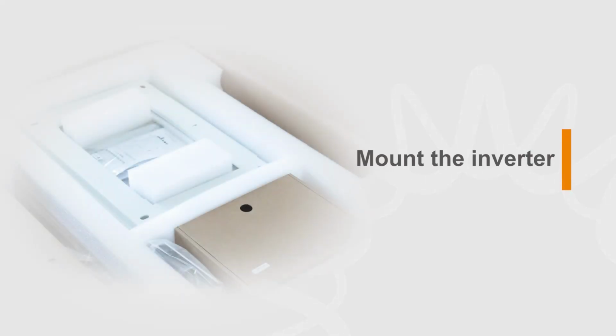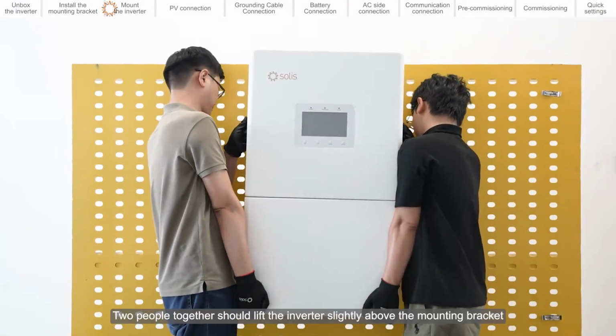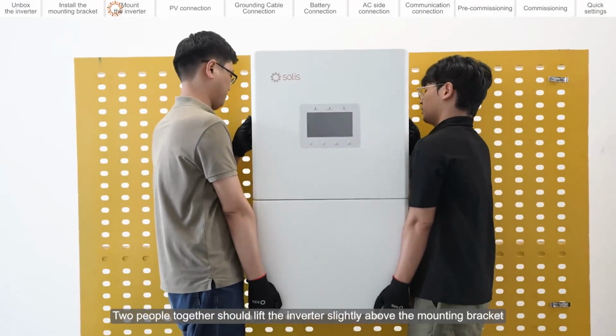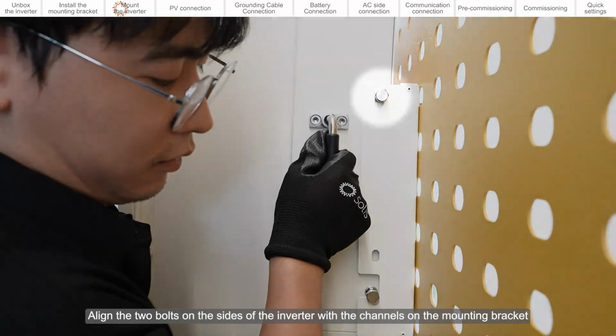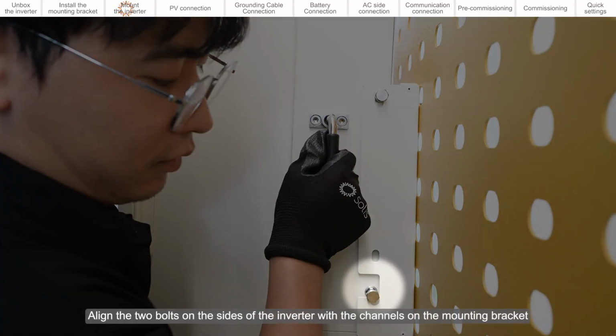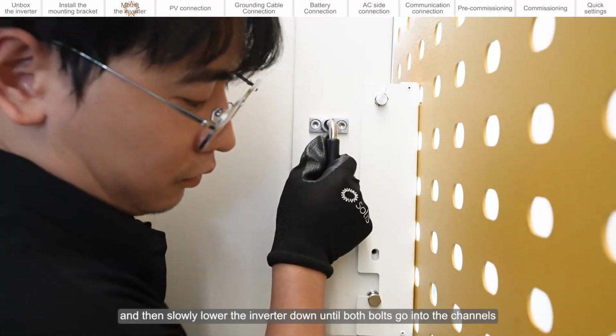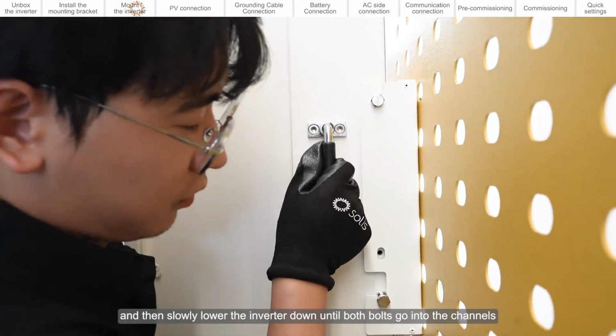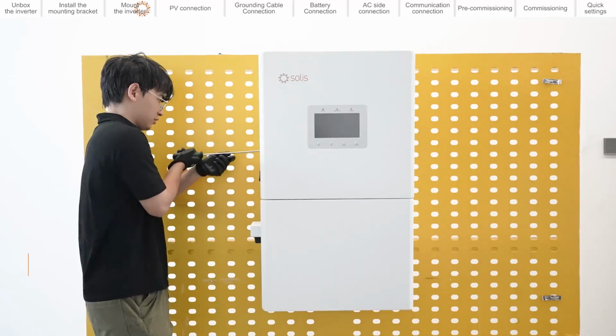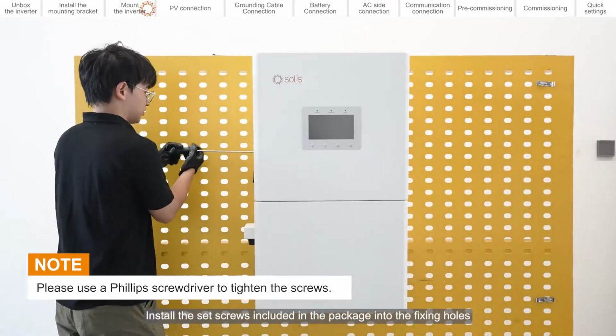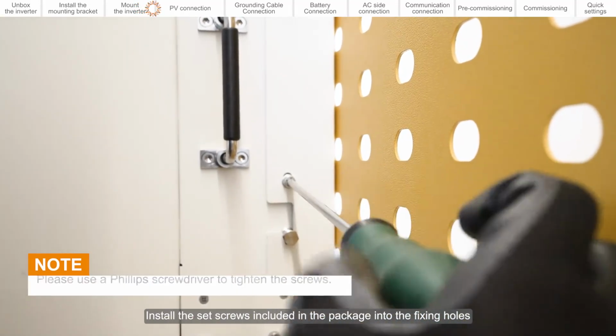Mount the inverter. 2 people together should lift the inverter slightly above the mounting bracket. Align the 2 bolts on the sides of the inverter with the channels on the mounting bracket, and then slowly lower the inverter down until both bolts go into the channels. Install the set screws included in the package into the fixing holes.